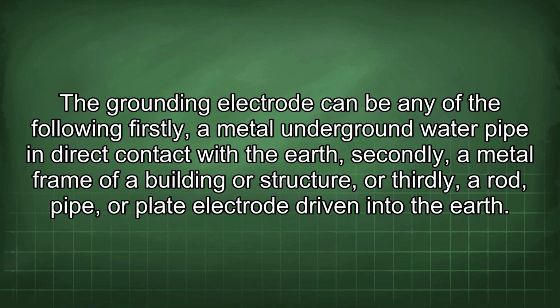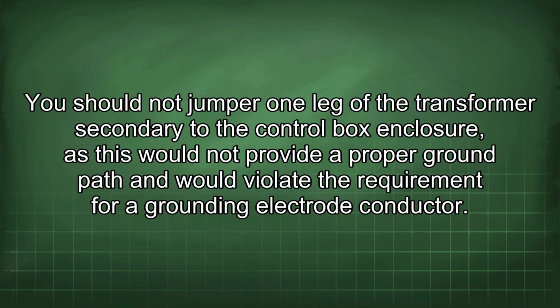The grounding electrode can be any of the following: firstly, a metal underground water pipe in direct contact with the earth; secondly, a metal frame of a building or structure; or thirdly, a rod, pipe, or plate electrode driven into the earth. You should not jumper one leg of the transformer secondary to the control box enclosure, as this would not provide a proper ground path and would violate the requirement for a grounding electrode conductor.